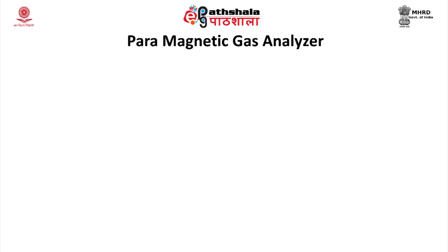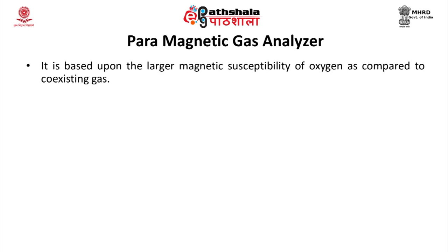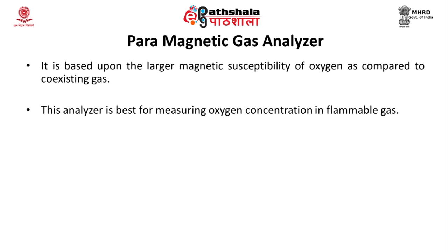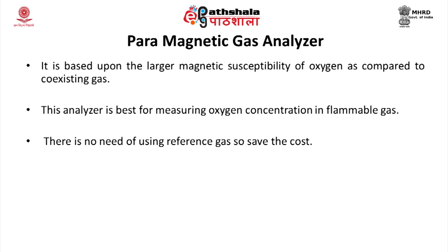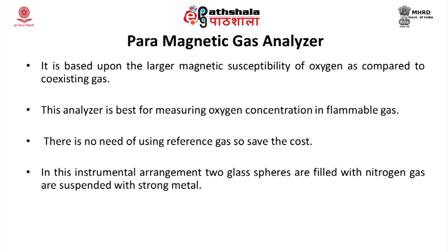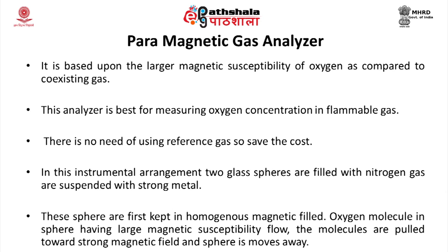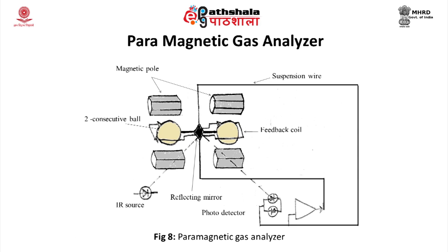The paramagnetic gas analyzer is based upon the large magnetic susceptibility of oxygen compared to other coexisting gases. It is best for measuring oxygen concentration in flammable gases, with no need for a reference gas, thus saving cost. In this arrangement, two glass spheres filled with nitrogen gas are suspended with a strong metal wire and kept in a homogeneous magnetic field. Oxygen molecules have large magnetic susceptibility and are pulled toward the strong magnetic field, causing the spheres to move away. This deviation is detected by a light source, reflecting mirror, and light-receiving element. Current flows through a feedback loop to return the spheres to the initial balanced state, and this current is proportional to the oxygen concentration.